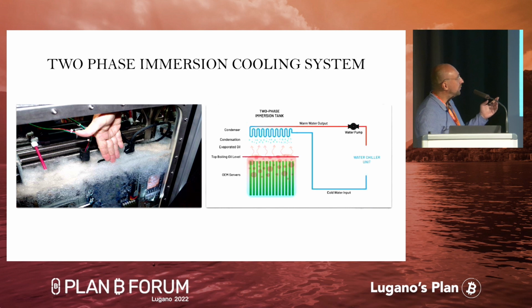Of course, if it boils at low temperature, you need to convert it back from gas to liquid form, and for that you need a condenser. Since it takes heat from the chip and boils at, for example, 40 degrees, the condenser temperature needs to be below 40 degrees. If it's 30 degrees outside, it won't be possible to use it naturally - you'll have to pay additional electricity for an air conditioner just to lower the condensation temperature.